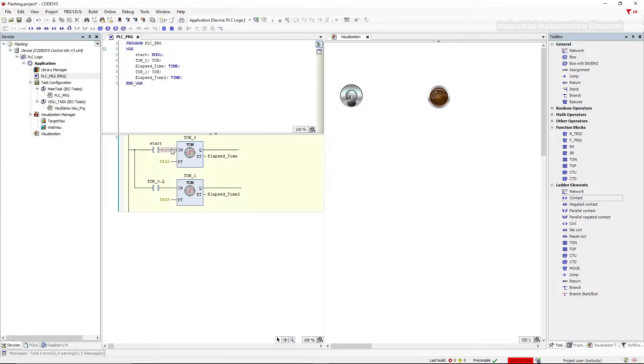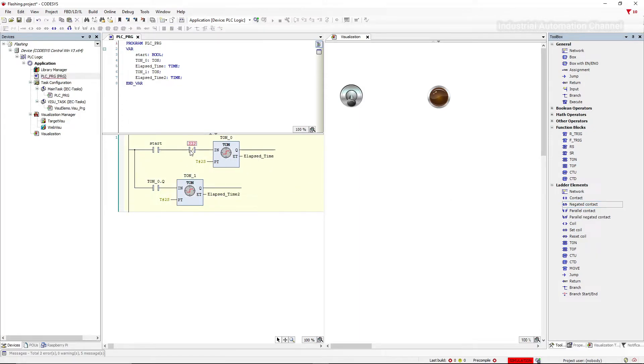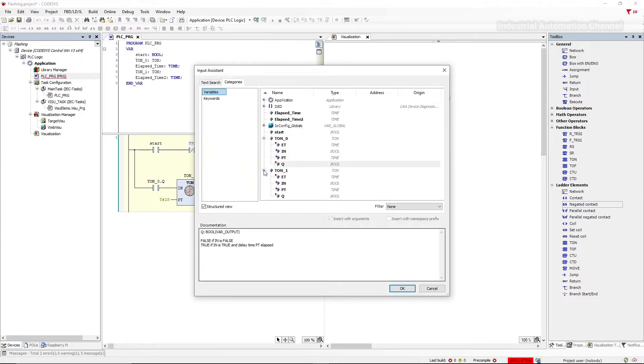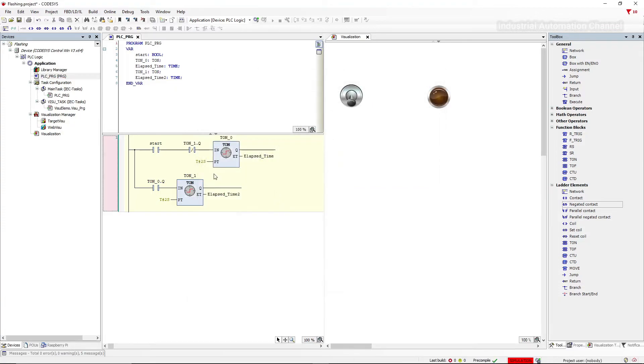I am going to add a NC contact before the first timer. It will be the output of the second timer. When the second timer is on after 2 seconds, the NC here will break the circuit and the first timer will be off.